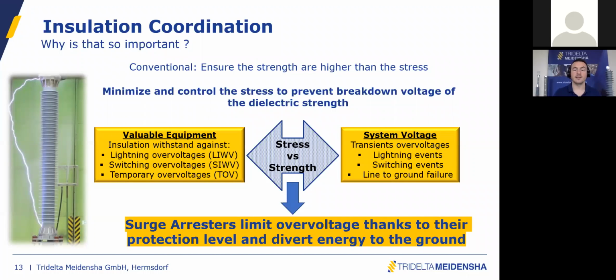Therefore, for me, there is a conventional definition for insulation coordination, but I would rather prefer to say that when it comes to surge arresters, the proper definition for insulation coordination should be to minimize and control the stress to prevent breakdown of the dielectric strength. The surge arresters limit the overvoltage thanks to their protection level and divert energy to the ground.